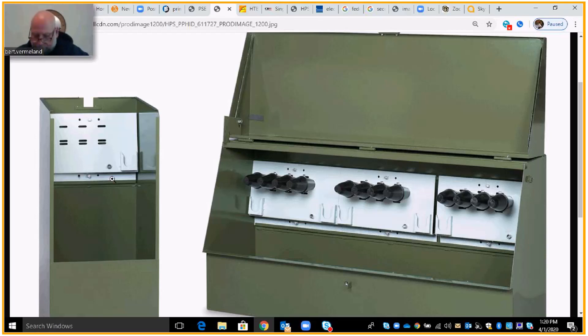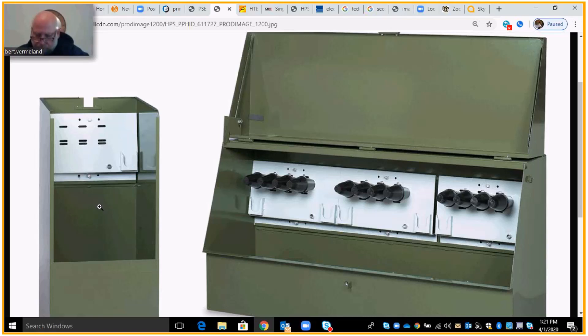Moving to the single-phase enclosure — just as the name implies, I'm only able to use one individual phase in here: either A, B, or C. I cannot put multiple phases inside this one. You can put any type of module you want. This module follows the same rules: I can come in with one A phase and out with A, out with A, and out with A. I've used just one single phase, but I can junction it in three different directions — inbound one direction, outbound one, outbound two, outbound three — all the same phase.